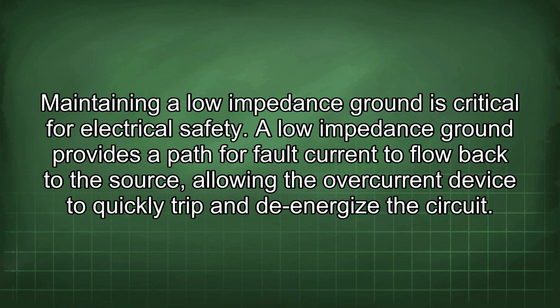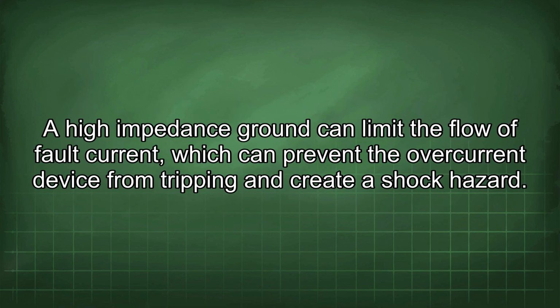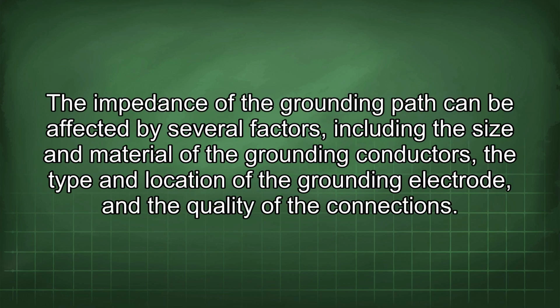A low impedance ground provides a path for fault current to flow back to the source, allowing the overcurrent device to quickly trip and de-energize the circuit. A high impedance ground can limit the flow of fault current, which can prevent the overcurrent device from tripping and create a shock hazard. The impedance of the grounding path can be affected by several factors, including the size and material of the grounding conductors, the type and location of the grounding electrode, and the quality of the connections.